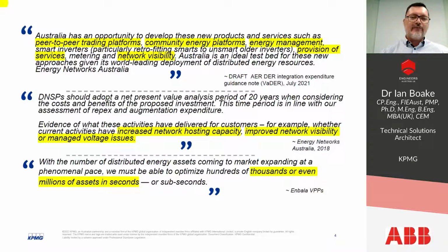Well, it's basically voltages and these power flows that traditionally used to move in one direction towards the load, from the generators to the load, but now actually flow back from households or DER into the network in a reverse direction. So a fairly important aspect that they've picked up on.